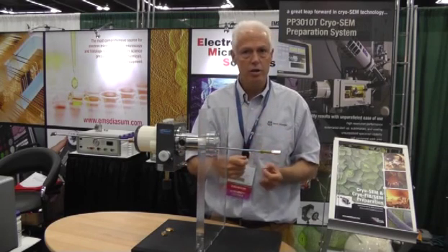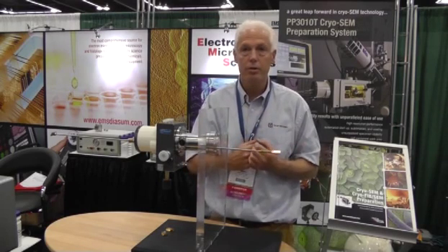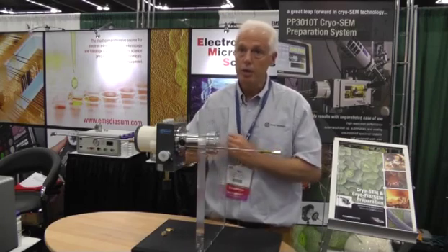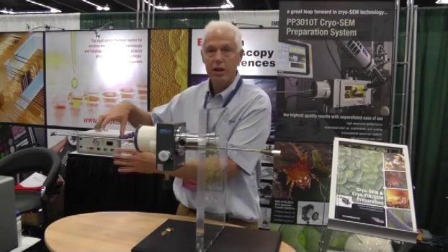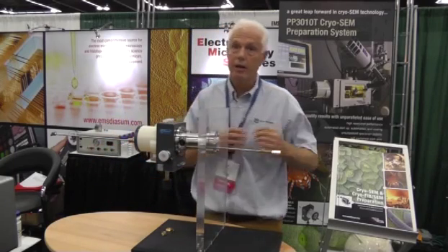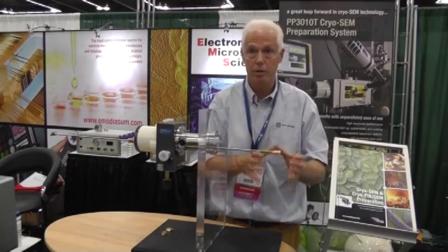If you want to look at wet samples, you can still do this, but you would need to have the optional slushing freezing device to first freeze the sample, do your transfer, and then transfer through into the microscope to the cold stage.